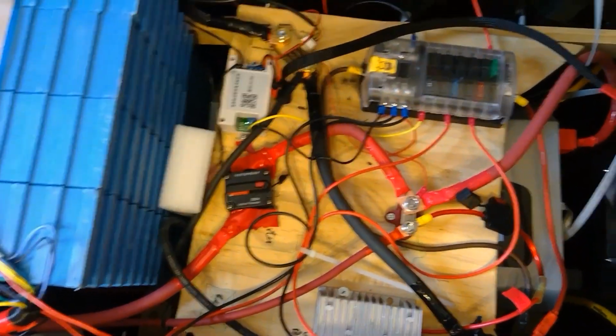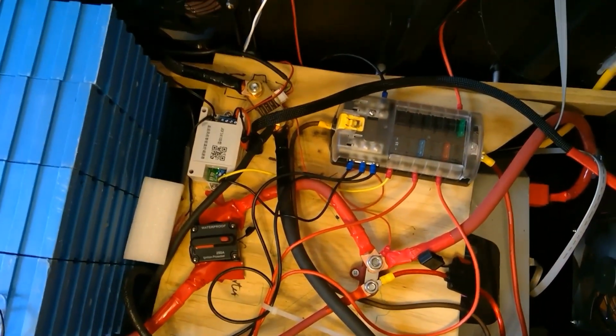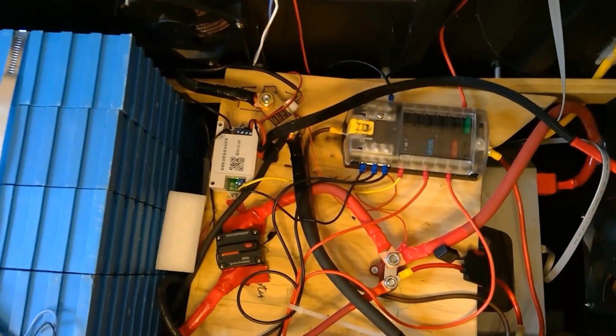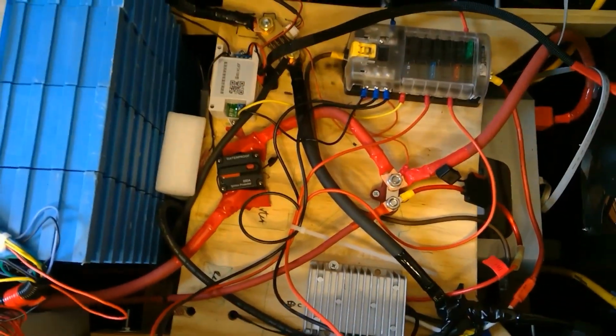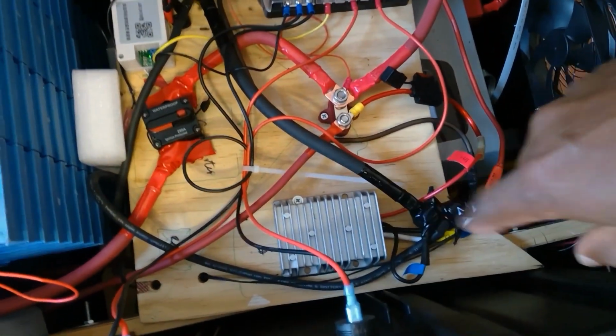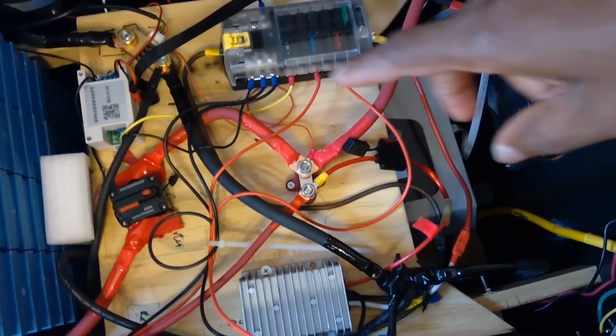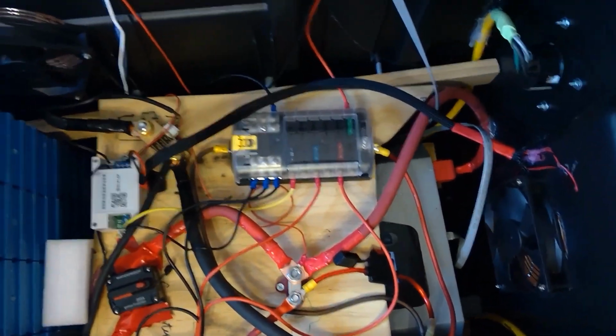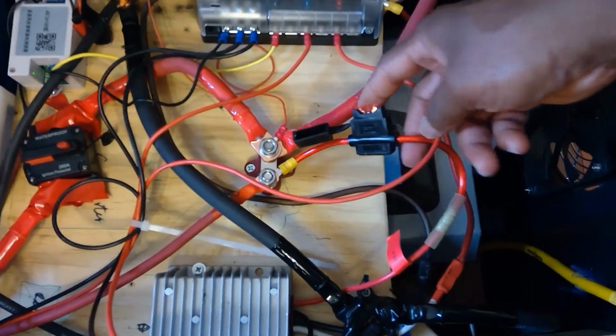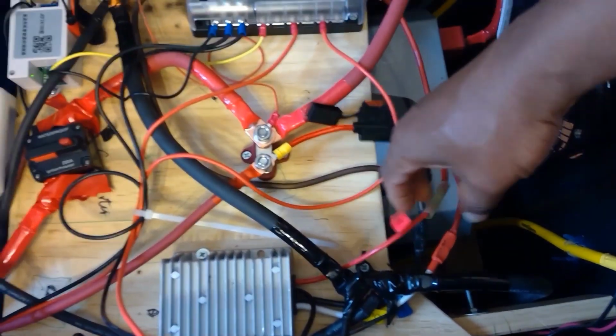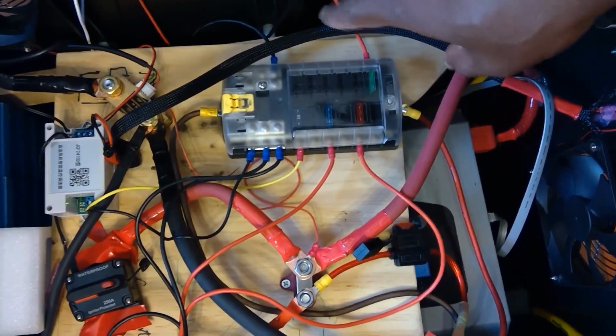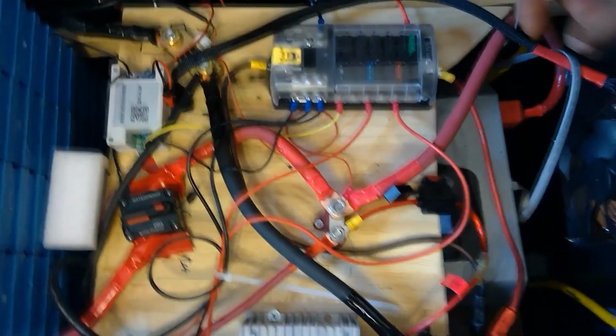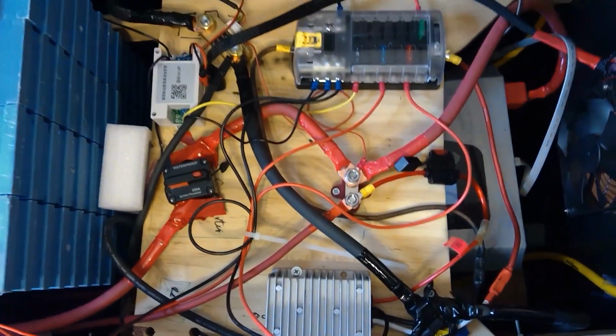This system is designed as a 24 volt system, but my DC outputs are 12 volt, so I needed a 40 amp converter to convert 24 volts to 12 volts. I have an inline 50 amp blade fuse to the converter, and fuses for my DC loads. I have two fans.